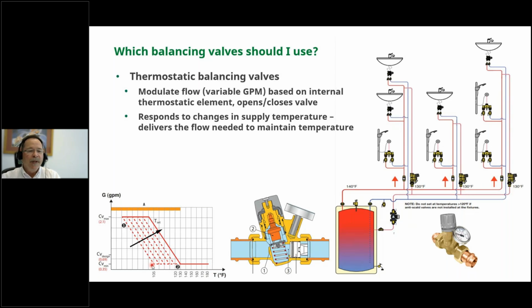So they actually open and they have a changing CV. So as the valve opens, it has more capacity. As the valve closes, it has less capacity, and it's all based on temperature. This gold colored cartridge in here is a sealed wax element. It's very sensitive to temperature, and when it gets cool, it contracts to open this seat right here, and when it heats up, it will expand and extend to close down this seat.